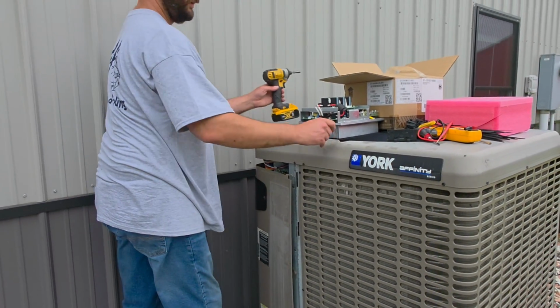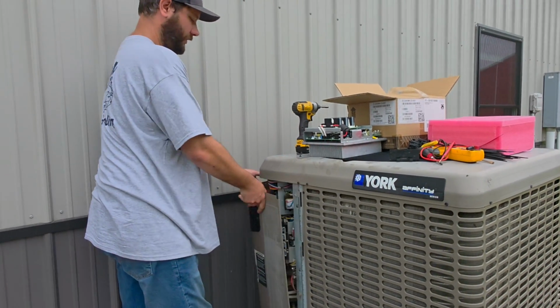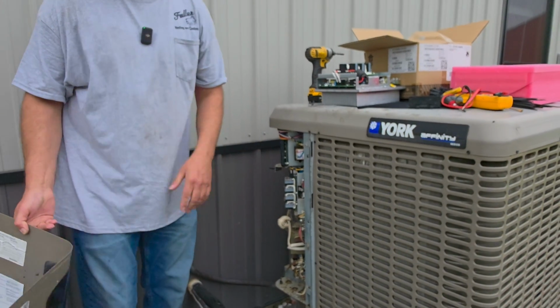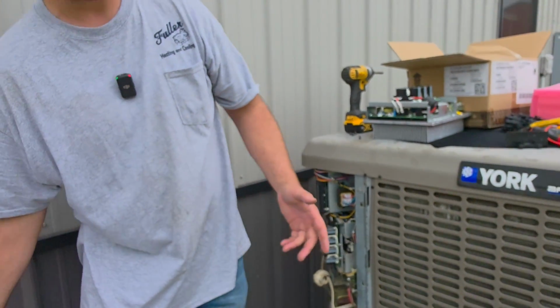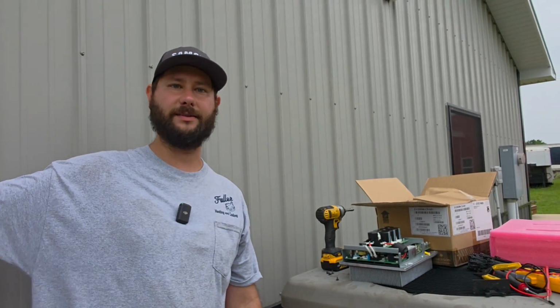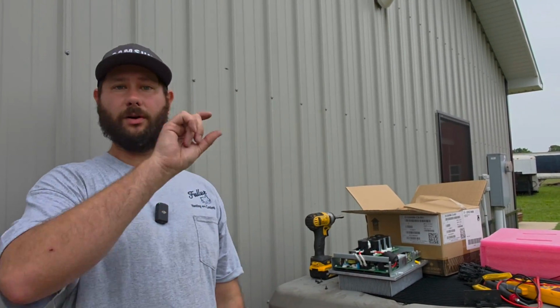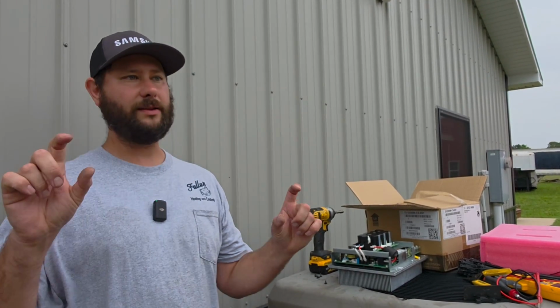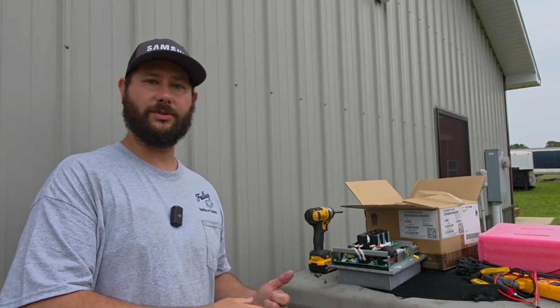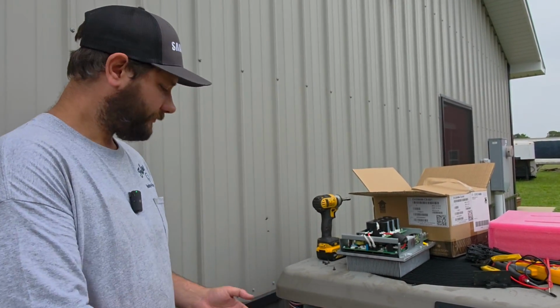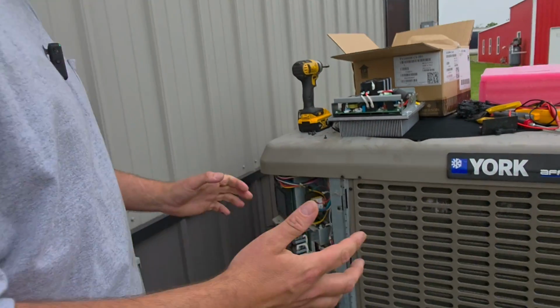How do we know the board's bad? We have an input, but no output, and we also have error codes throwing. The thermostat inside was communicating, and the customer could see it throwing an error code indicating a problem with the outdoor section. When I got here, I checked the voltage going into the board, then checked the output, and there was none. That's the easiest way to tell.